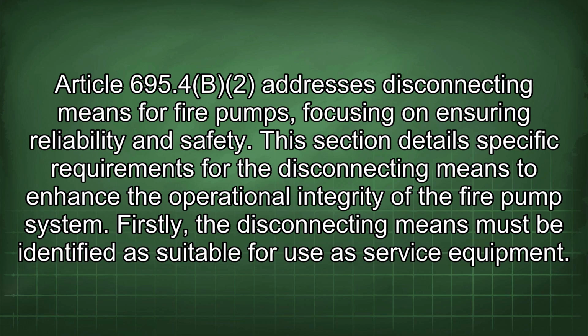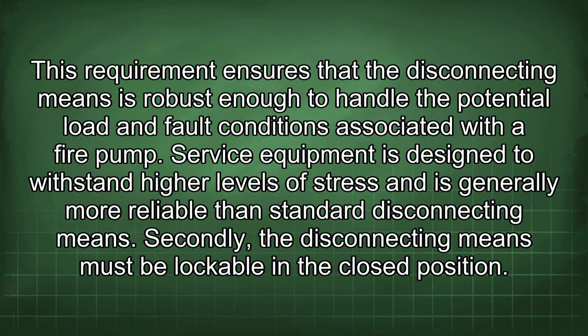Firstly, the disconnecting means must be identified as suitable for use as service equipment. This requirement ensures that the disconnecting means is robust enough to handle the potential load and fault conditions associated with a fire pump. Service equipment is designed to withstand higher levels of stress and is generally more reliable than standard disconnecting means. Secondly, the disconnecting means must be lockable in the closed position.